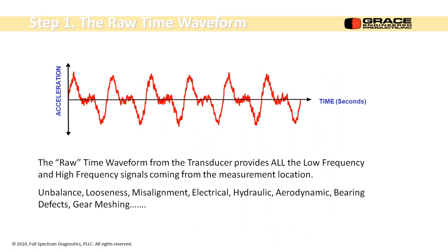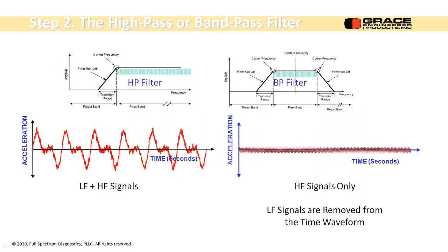I got about 8 minutes left. We pull the same time waveform, goes into our analysis tool, and we do a little software magic to filter it and change it. So the raw signal has all the residual imbalance, looseness, misalignment, electrical, hydraulic, bearing defects, gear meshing. It has everything in it, okay? We don't care about the big wiggles. We're looking for the real high frequency stuff that's riding on top of it, okay? So we have to put it through a filter. Typically, it's a high pass filter or a band pass filter.